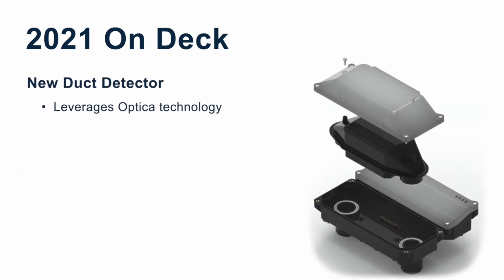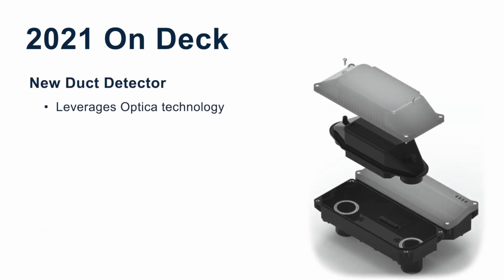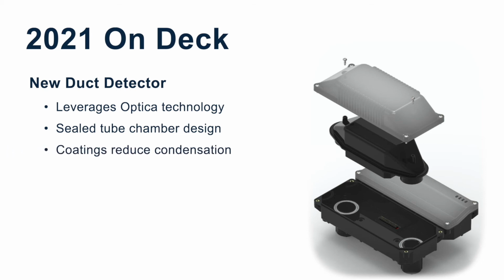Our next program is the Intelligent Duct Detector. We are leveraging our Optica technology by creating a tube with the optical components which plug directly into the inlet and outlet ports. This tube creates a tunnel where we sense smoke but has very few obstructions, so it minimizes the buildup of dirt. Added to this, the plastics are made of conductive material which has proven itself to reduce dirt buildup in our standard spot detectors. Plus, a coating is used to reduce the adherence of moisture to the insides of the chamber, helping to reduce any condensation that might occur.